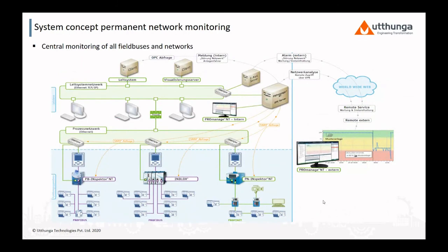Okay, moving forward with the inspector, now everyone wants to do centralized monitoring. Now in Industry 4.0, everyone talks about Industry 4.0, the plant, the shop floor activities, I need to get them at remote locations. Then you can move forward with our software, that is ProManage software. Every master system requires one inspector, every one master, one inspector, means one network segment requires one inspector. If in your premises you have 5 or 10 master systems in PROFIBUS, and you are using this software, you can get the overview of all networks in remote locations.